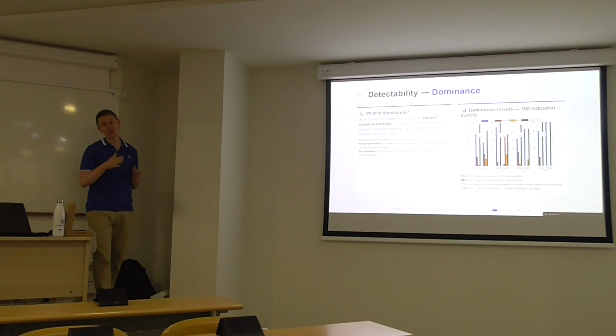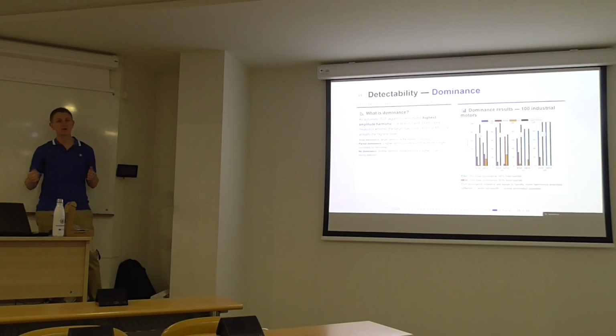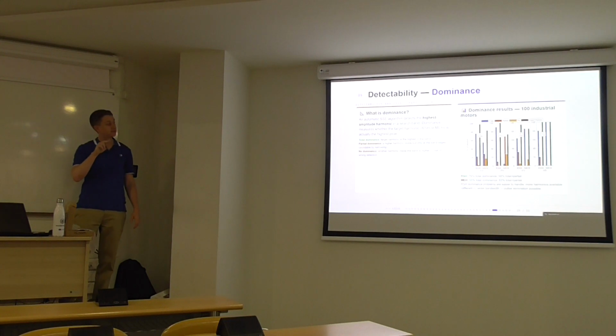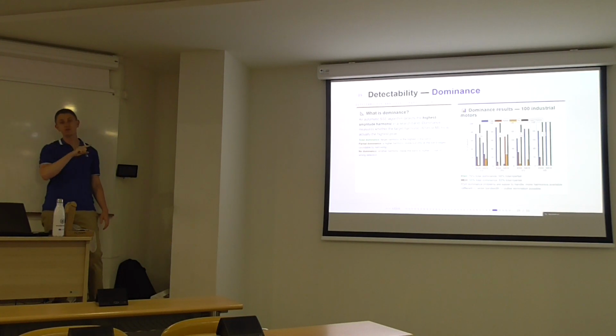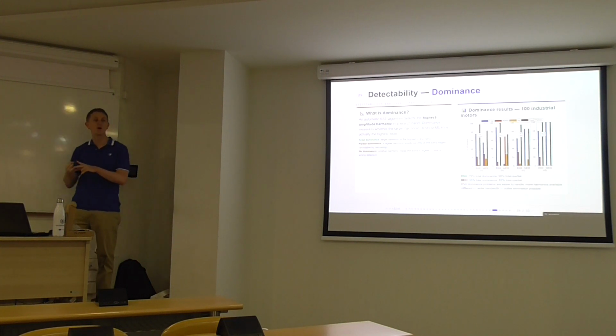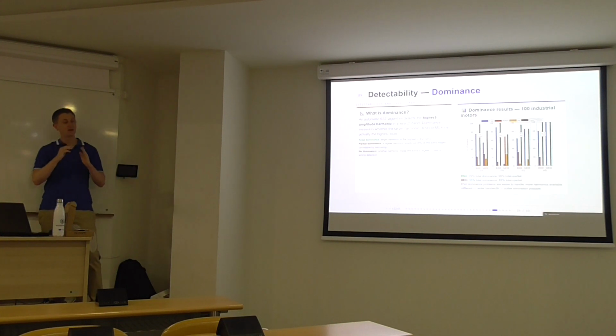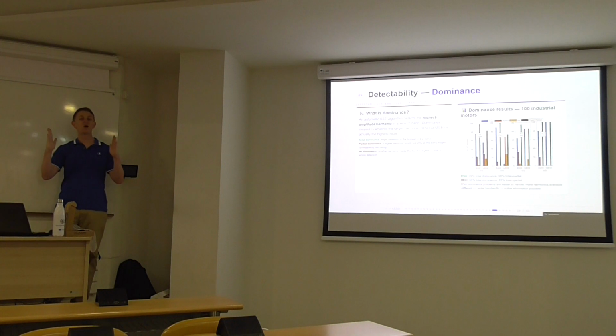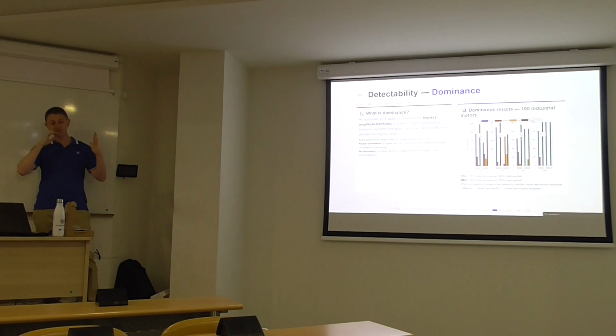In addition, rotor load harmonic dominance problems are easy to deal with, because in the case of mixed eccentricity you only have two harmonics, but for rotor load harmonics you have multiple of them, linked to nu equal to 1, nu equal to minus 1, nu equal to 3, etc. And in addition, the bandwidth of the rotor load harmonic is much higher than that of the mixed eccentricity harmonic. What is the bandwidth? The bandwidth is how much the rotor load harmonic can move from no load to full load. So that bandwidth is much bigger than in the case of the mixed eccentricity harmonic.